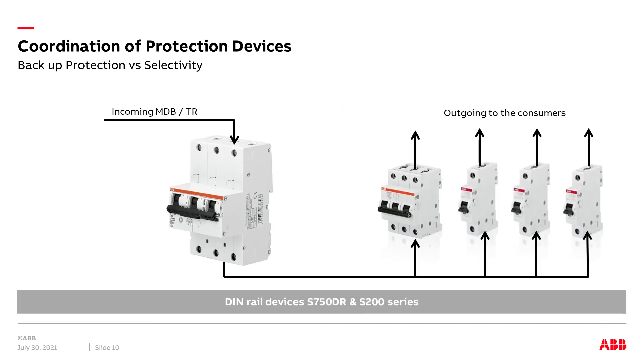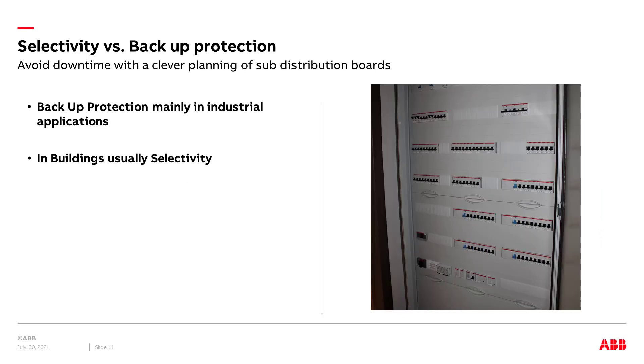The main application of the S750 is the protection of the incoming feeder of houses; however, it can also be used in locations where safe and reliable power supply is paramount — for example, the protection of a hotel section with several rooms. As mentioned earlier, backup protection is mainly used in industrial applications where you can accept high short circuit ratings. In buildings, however, it is common to coordinate protection devices for selectivity.